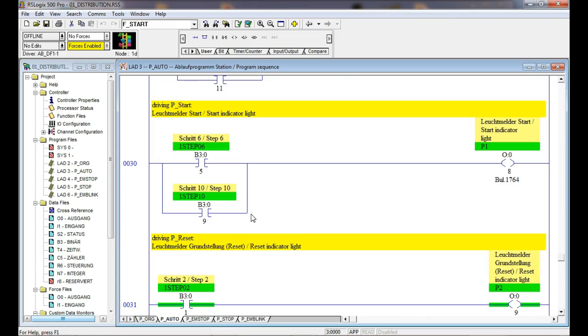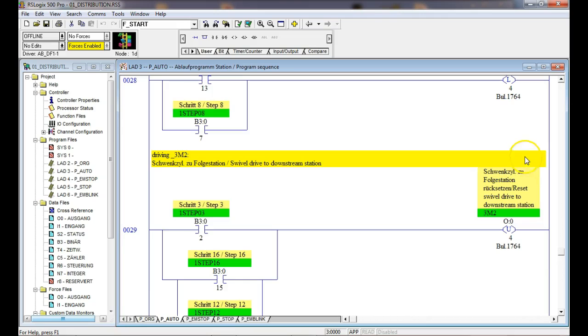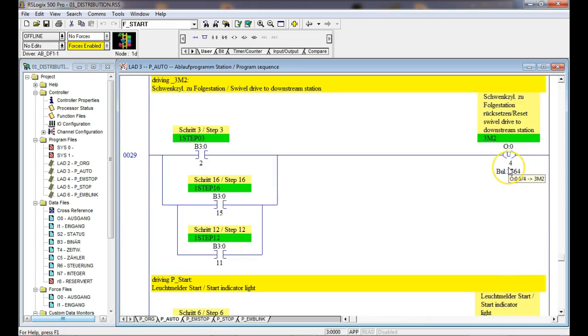So it's actually easier to program it to have one rung that does what? Latches it, and one rung to do what? Unlatch it. And that way you can divide this. So what's required to latch it, you would put all that in one rung by itself, and what's required to unlatch it, you would put in the other one, right? That makes sense. So what would unlatch this? Either this is true or this is true or this is true.